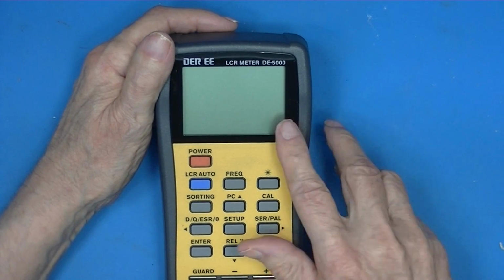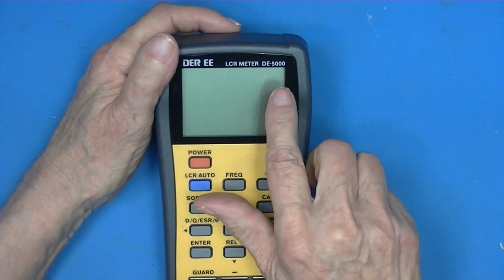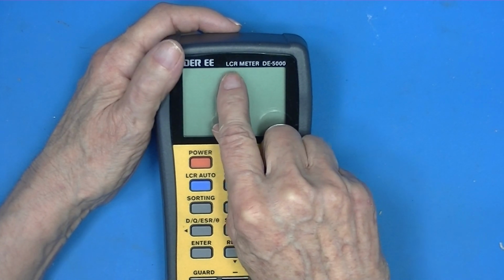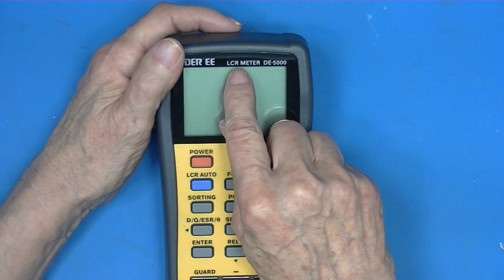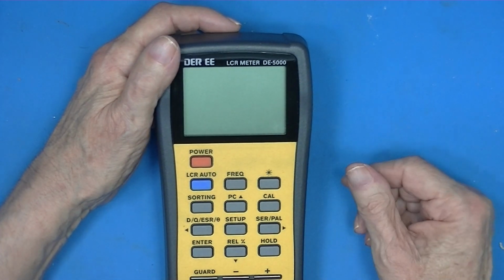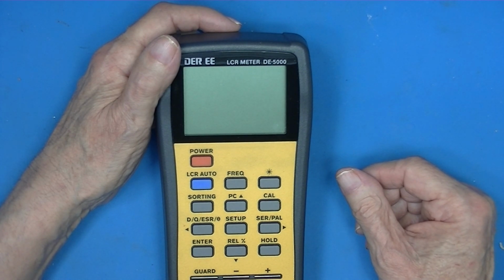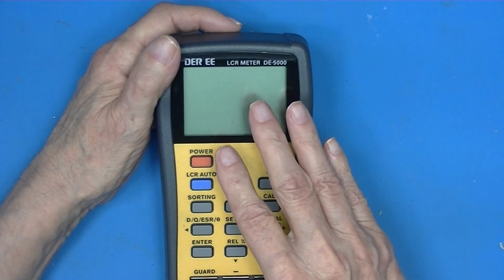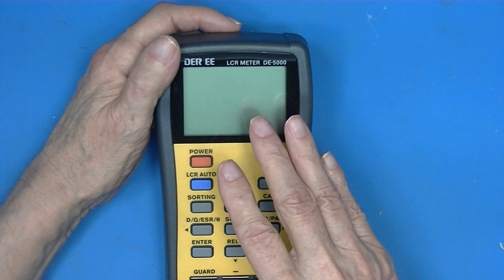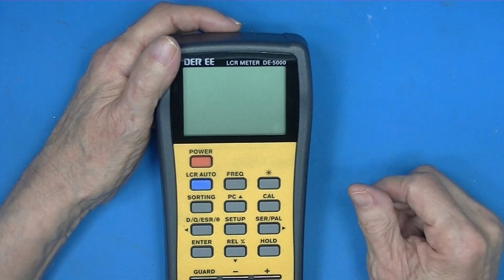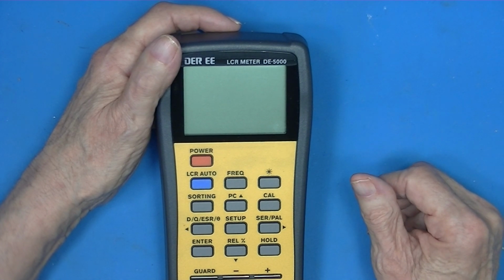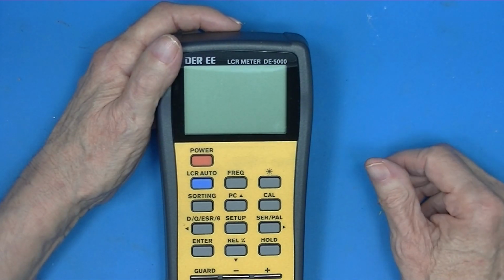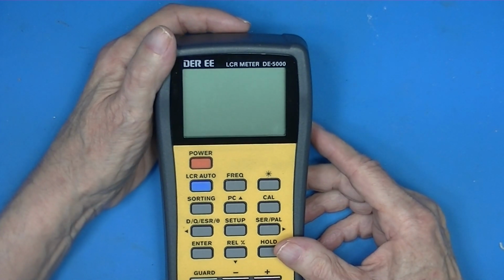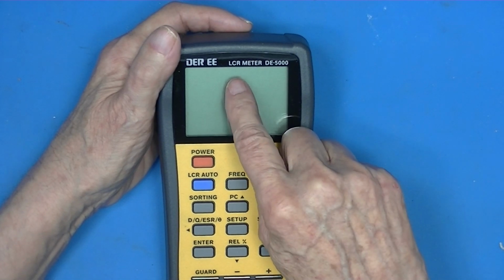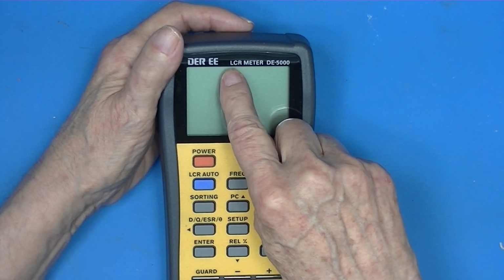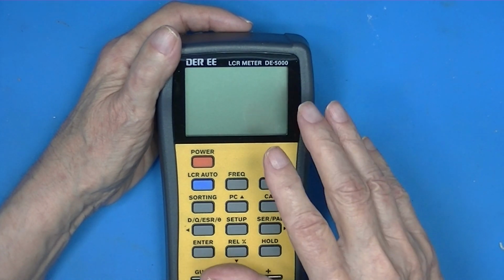So this is a LCR meter. It's capable of measuring values of inductance, capacitance, and or resistance simultaneously or individually. And in order to do that, it uses an exciting current that's alternating current. Up to now, on this bench, we've used DC current for excitation. But because we're measuring characteristics of impedance, inductance, and capacitance, we have to use AC.